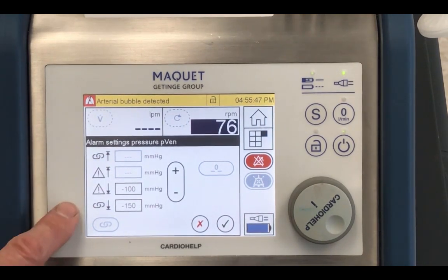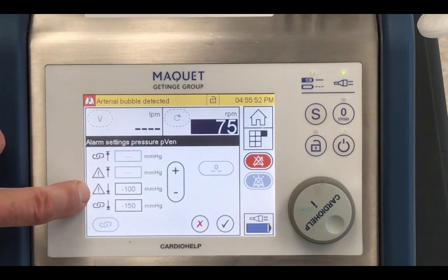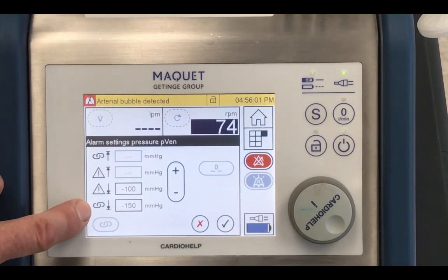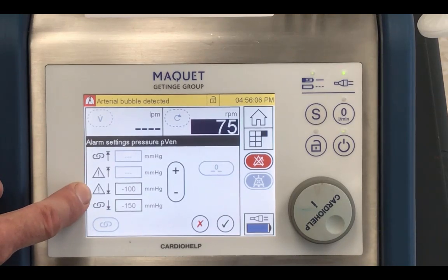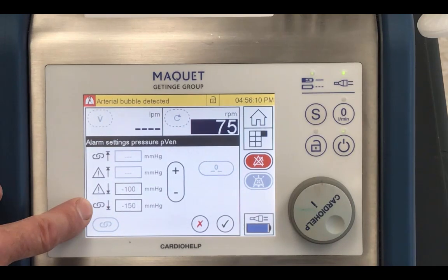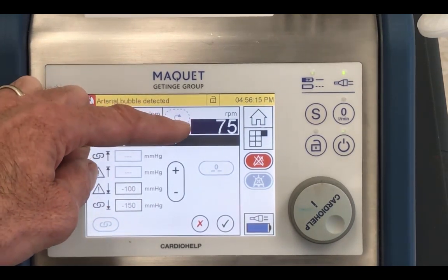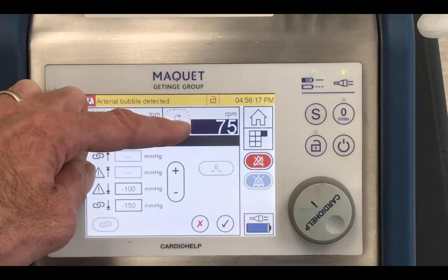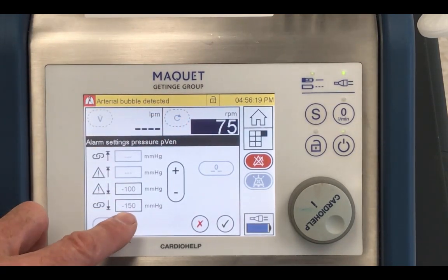So right now, what we're seeing is that this is the venous line pressure. It should run in negative. So this system was last set up to have an alarm at 150, and then an alarm at 100, and have an intervention at 150. So what that's going to do is give us an audible alarm and tell us, hey, your line pressure is now minus 100, but it's not going to change anything until it reaches minus 150.